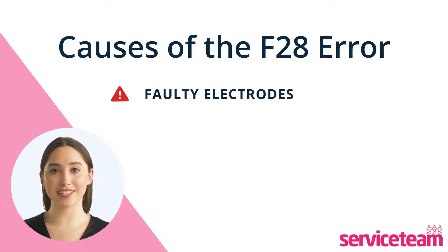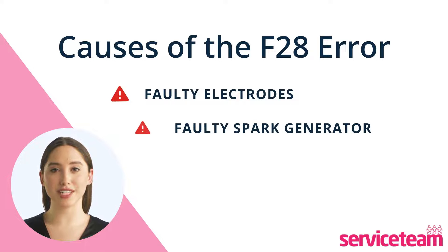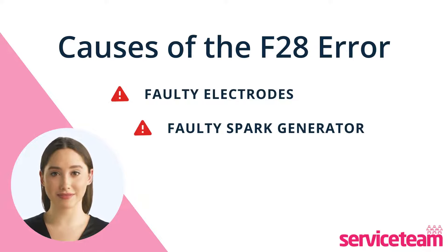If your boiler shows an F28 fault, it could be due to a faulty spark generator, which ignites the gas. Replacing the faulty part usually solves the issue.